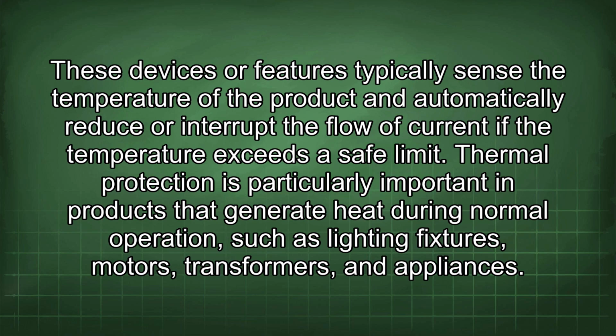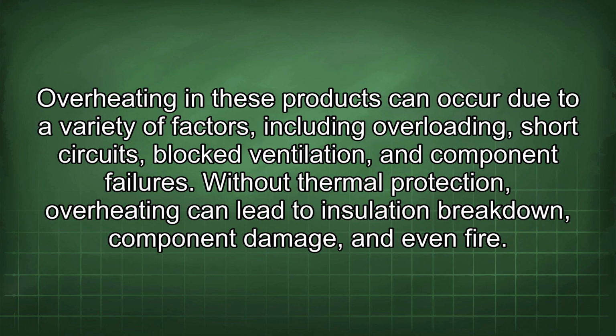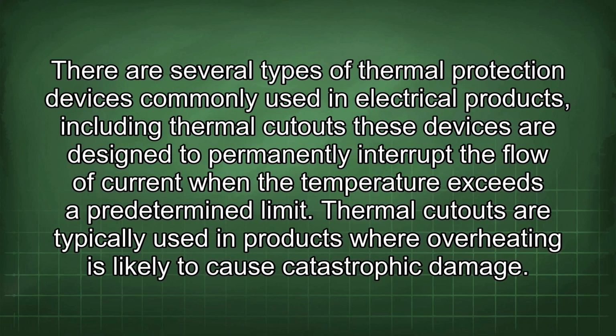Thermal protection is particularly important in products that generate heat during normal operations, such as lighting fixtures, motors, transformers, and appliances. Overheating in these products can occur due to a variety of factors, including overloading, short circuits, blocked ventilation, and component failures. Without thermal protection, overheating can lead to insulation breakdown, component damage, and even fire. There are several types of thermal protection devices commonly used in electrical products, including thermal cutouts. These devices are designed to permanently interrupt the flow of current when the temperature exceeds a predetermined limit. Thermal cutouts are typically used in products where overheating is likely to cause catastrophic damage.